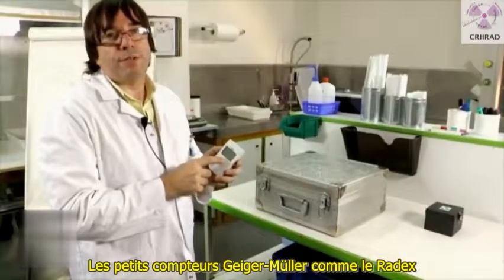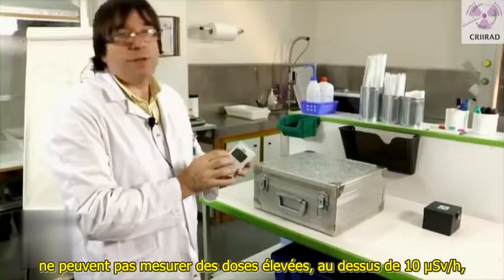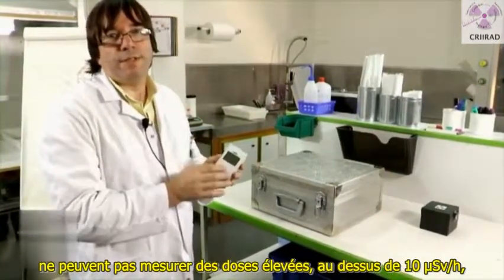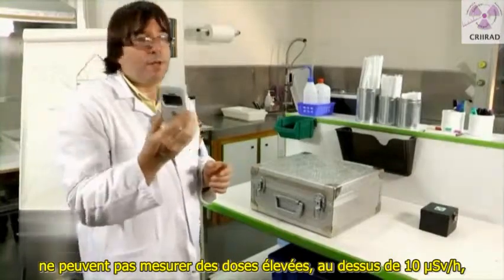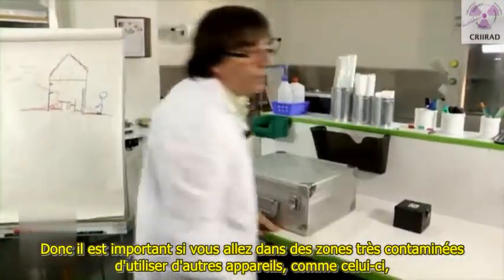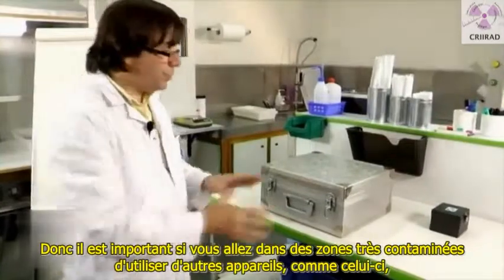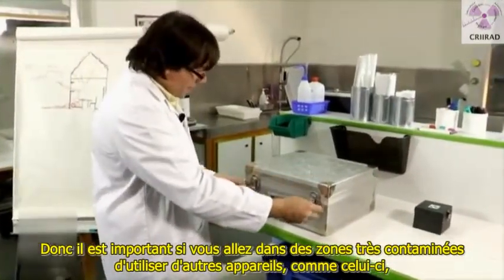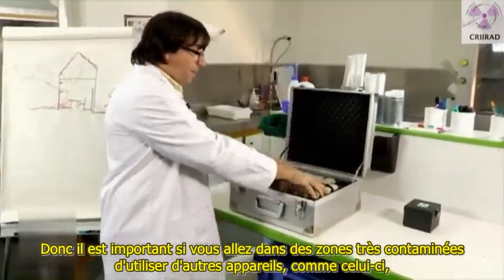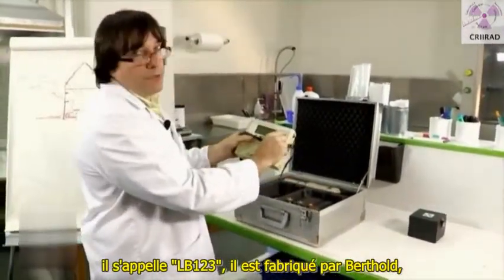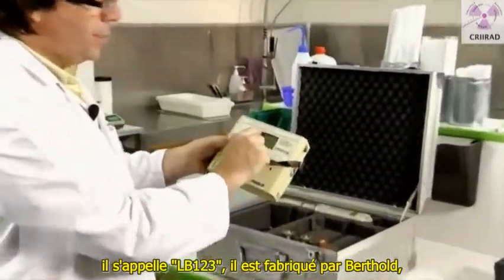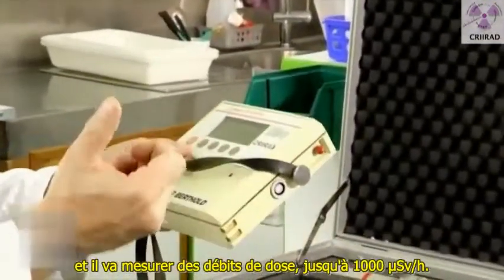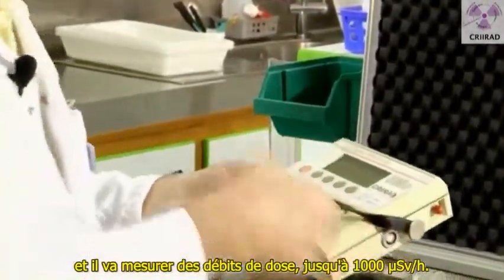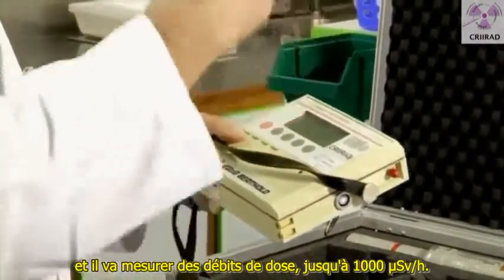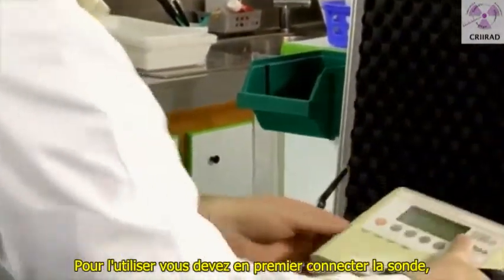Geiger-Müller counters like the Radex cannot measure high doses above 10 microsievert per hour. So it's important, if you go to really contaminated places, to use other devices like this one. It's called LB123. It's manufactured by Berthold, and it will measure dose rate, but it can measure dose rates as high as 1,000 microsievert per hour. So to use it, you first have to connect the probe.